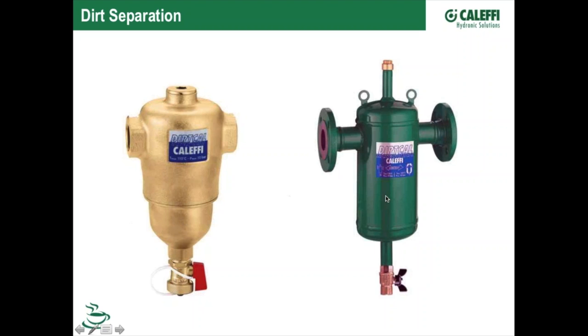This is the same concept over here, again, a larger, welded steel version with flanges on it, rings, so if you want to hang that from some clevis hangers and some threaded rod, we make it easier for you to do that. A nice valve on the bottom so you can flush it out and get a good flow out of that. These valves on the bottom could also be used to inject chemicals into the system if you do need to put a cleaner in there and clean up the system, or if you want to put an inhibitor in your system, water can go into that as well as it comes out, so that is a nice point to dose it.